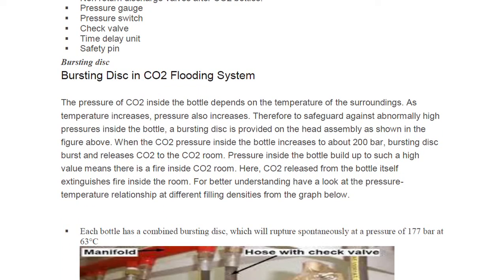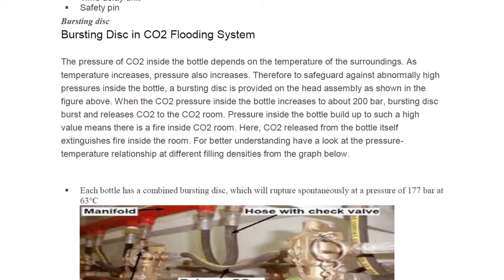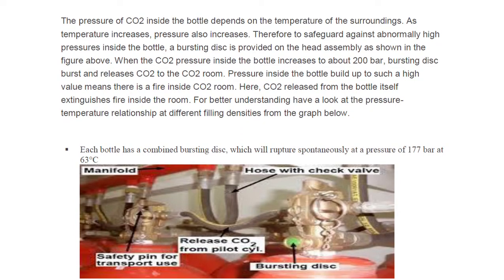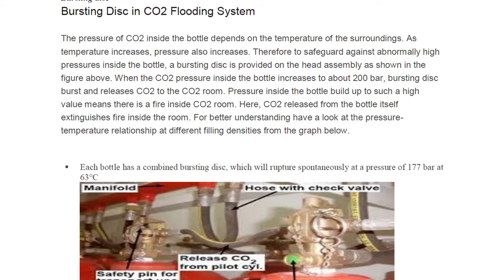First, let's talk about the bursting disk, which is very important. The pressure of CO2 inside the bottle depends on the temperature of the surroundings — as temperature increases, pressure also increases. Therefore, to safeguard against abnormally high pressure inside the bottle, a bursting disk is provided on the head assembly. When CO2 pressure inside the bottle increases to about 200 bar, the bursting disk bursts and releases CO2 to the CO2 room.